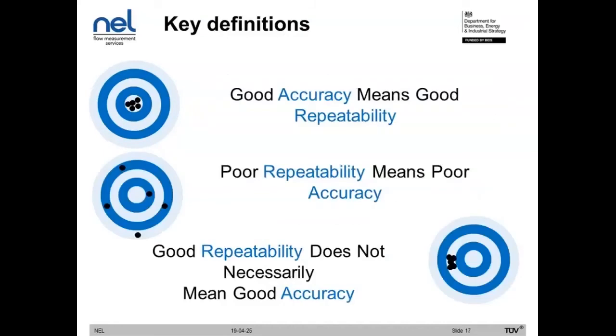In terms of the relationship between accuracy and repeatability, if you have good accuracy, then you also have good repeatability. This is because if you have successive measurements that are very close to the true value, then those measurements must also be close together as well. So there are consistent readings from the measuring device. If you have poor repeatability, then it is not possible to have good accuracy. Again, this is because you have a scatter of results, so if every measurement is different from the last, then they can't all be close to the true value.